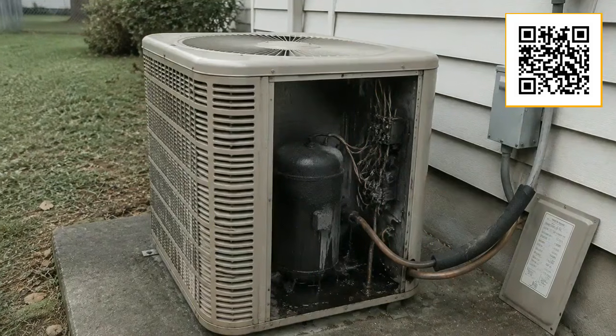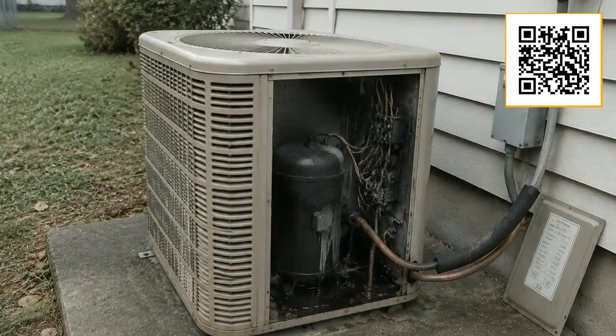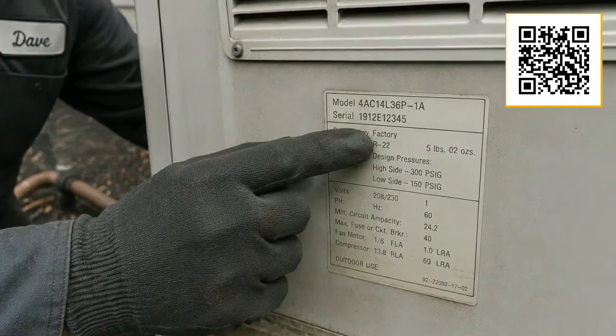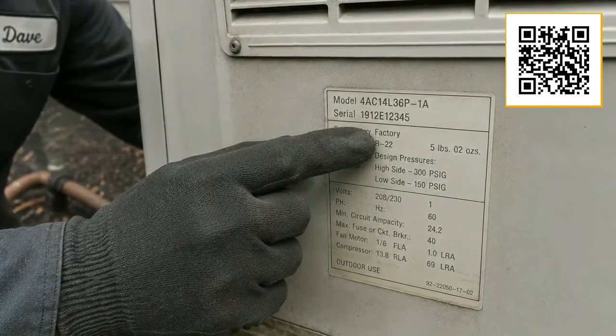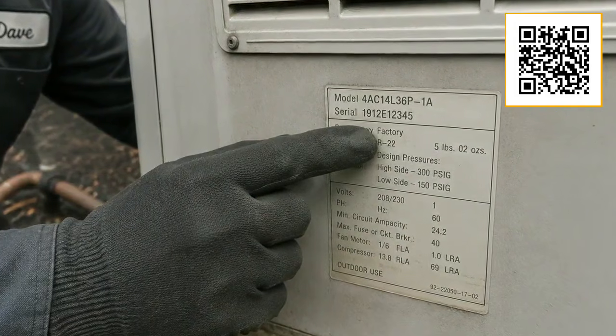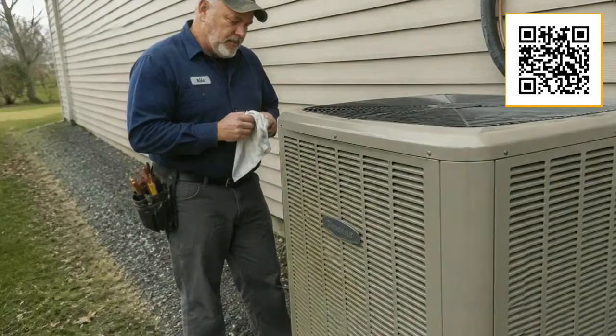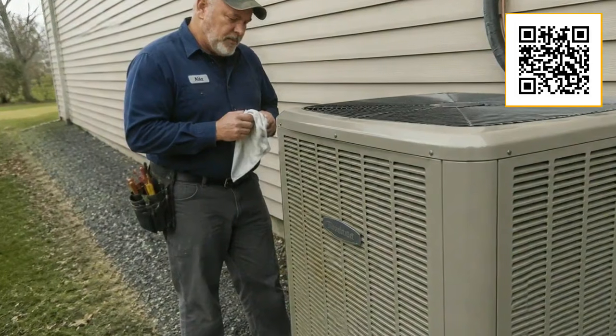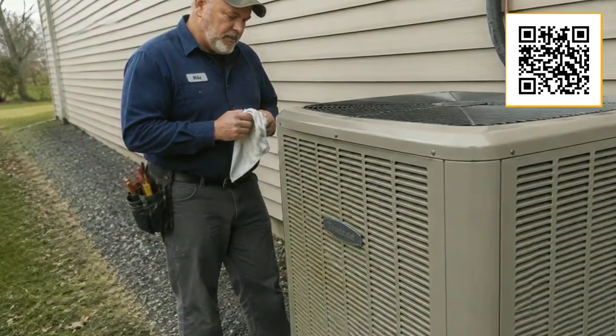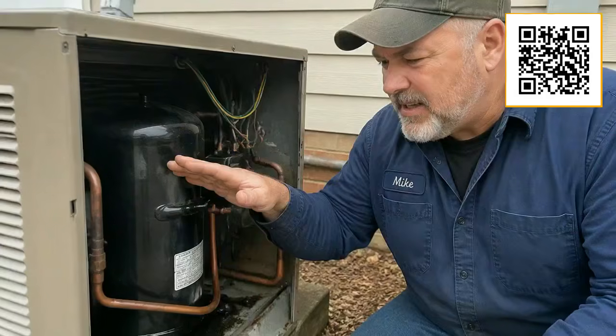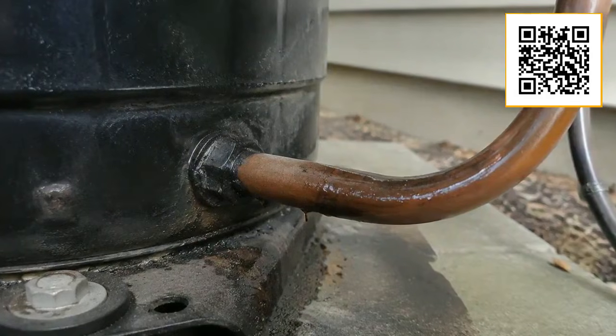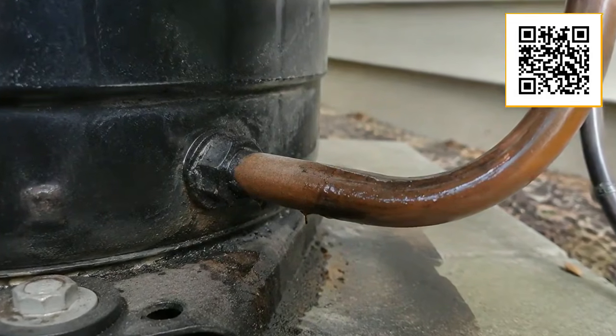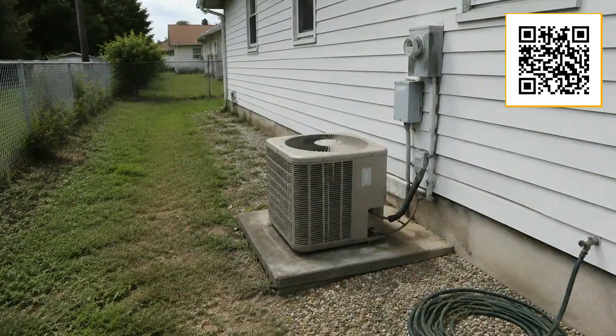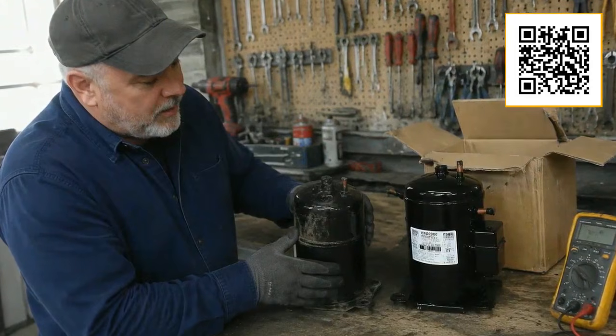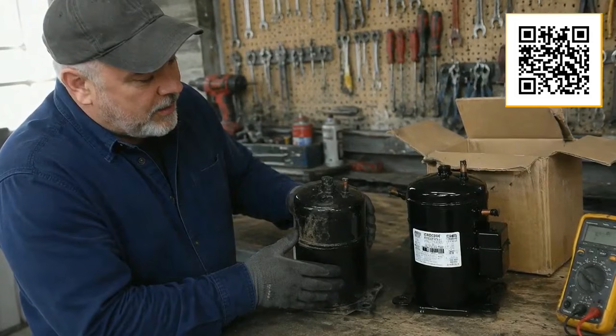I have seen oversized units fail in as little as 5 or 6 years because of this, while a properly sized unit in the same home could easily run 15 or more years without major trouble. A 3-ton unit dropped into a home that only needs 2 tons is not a safety cushion, it is a liability. Every time that oversized compressor kicks on, it draws a surge of current, heats up fast, and shuts down before the oil has fully circulated through the system. Do that 50 times a day for 5 summers, and you have worn out a component that costs anywhere from $800 to over $2,000 to replace.